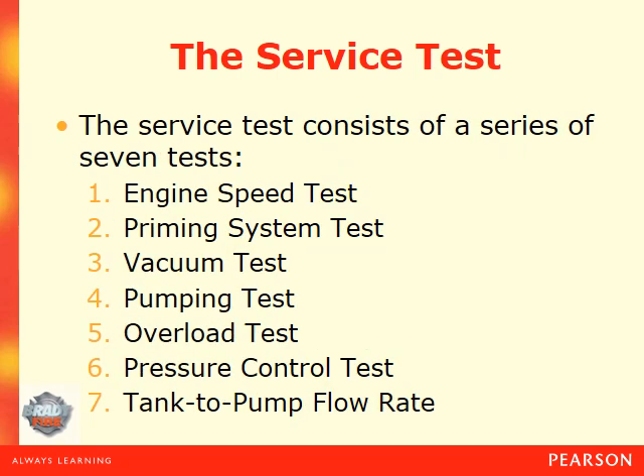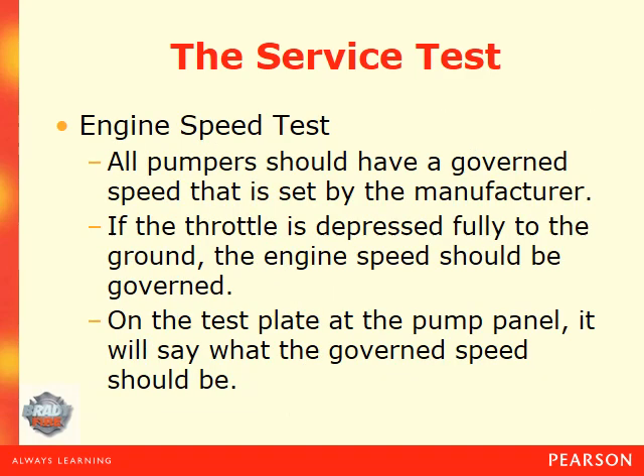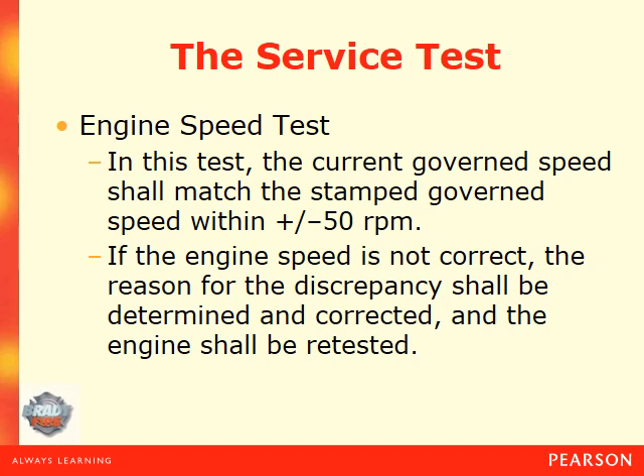The service test consists of a series of seven tests: engine speed test, priming system test, vacuum test, pumping test, overload test, pressure control test, and tank-to-pump flow rate. For the engine speed test, all pumpers should have a governed speed set by the manufacturer. The test plate at the pump panel will indicate what the governed speed should be. The current governed speed shall match the stamped governed speed within plus or minus 50 RPM. If the engine speed is not correct, the reason for the discrepancy shall be determined and corrected, and the engine shall be retested.